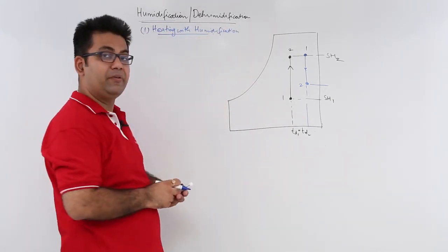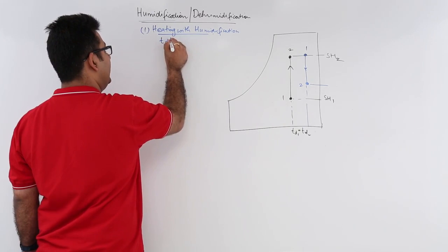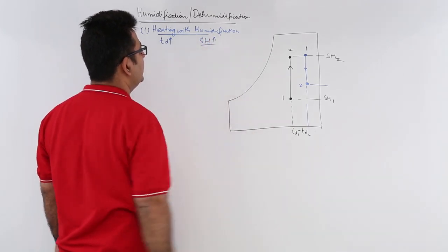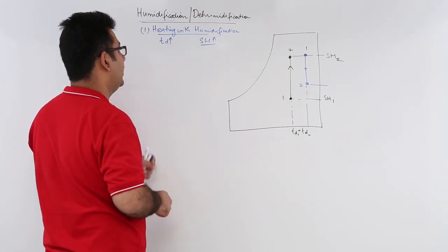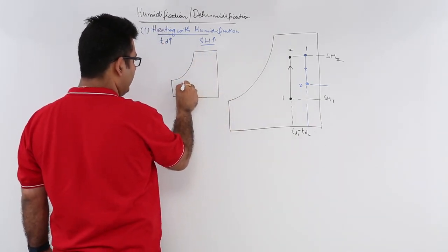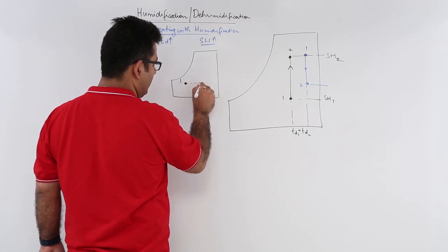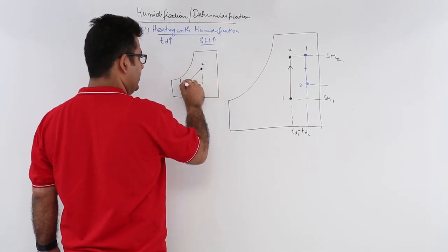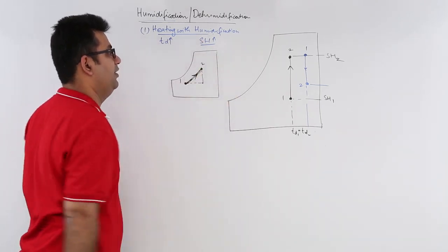Let me draw this chart space. Now we have to heat it and also humidify it. Heating means the dry bulb temperature has to go up, and humidification means the specific humidity has to go up. So you are at a starting point, you first increase your DBT to an intermediate state, and then you humidify it to reach the final point. This line indicates that you have heated it and also humidified it.